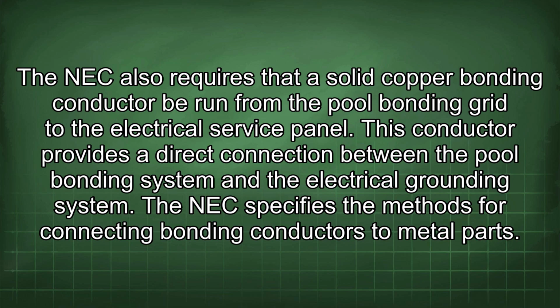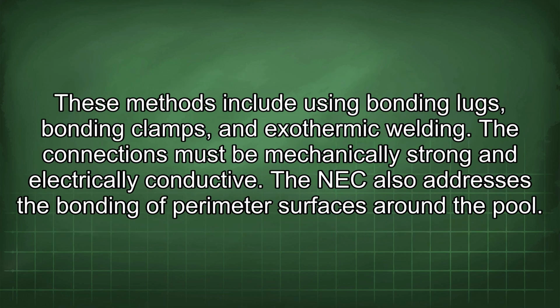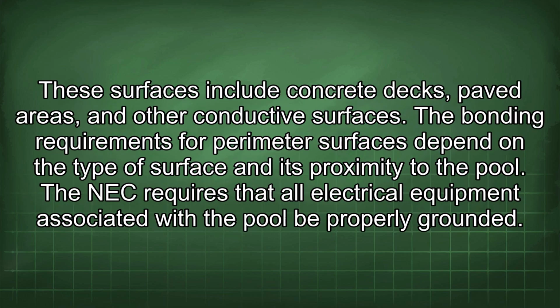The NEC specifies the methods for connecting bonding conductors to metal parts. These methods include using bonding lugs, bonding clamps, and exothermic welding. The connections must be mechanically strong and electrically conductive. The NEC also addresses the bonding of perimeter surfaces around the pool. These surfaces include concrete decks, paved areas, and other conductive surfaces. The bonding requirements for perimeter surfaces depend on the type of surface and its proximity to the pool.